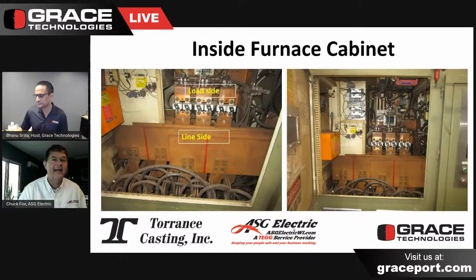That configuration of the cabinet was indeed the challenge. The broad question from the plant manager or facility manager at the time is, how do I open the door and do inspection when it's 119 calories? The result is we probably don't want people in that cabinet unless we can be absolutely assured that we are in an electrically safe work condition as defined by the 70E standards. So how do we do that in this particular application, this particular piece of equipment?